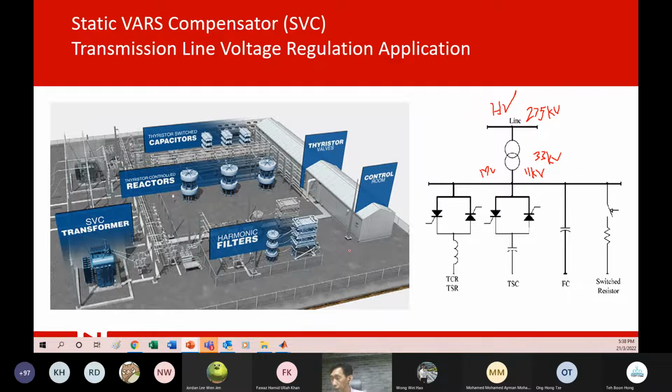It's usually situated at the switch yard. Okay, usually near what we call the PMU in Malaysia, Pencawang Masuk Utama, the substation that actually receives or transmits the transmission line. Okay, so it's higher up in the hierarchy of the substation. So usually they will have a control room. They will have the thyristor valve. We see all here, they are actually quite big. I mean, they're stacked together so that they can handle thousands of watts. So usually they put it inside the room here.